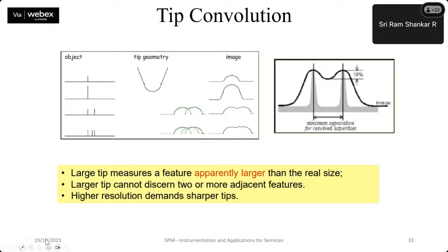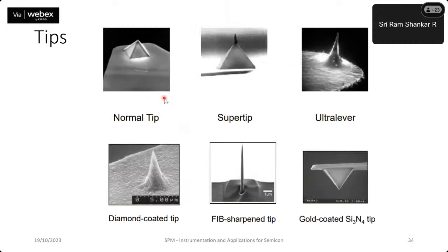If you have two wires placed close to each other, you'll see two balls that are closely spaced. This is how the image would look. And if there are several such wires placed close together, you won't even be able to distinguish between them. So the tip geometry ultimately decides the resolution with which you can capture images.